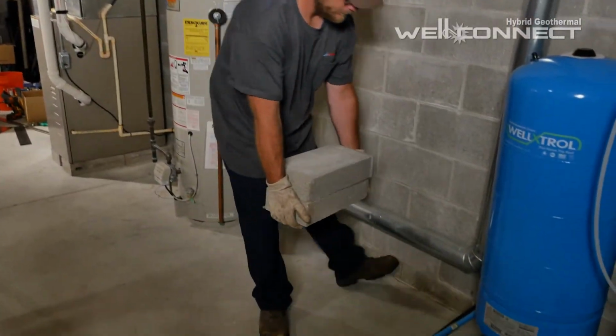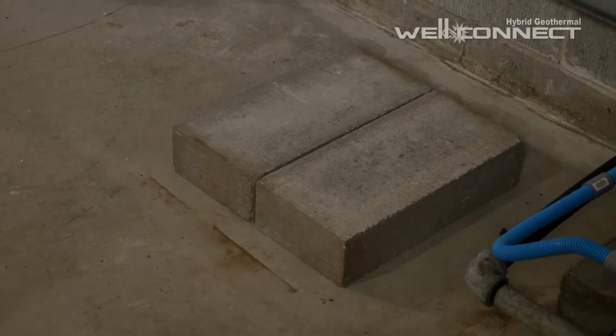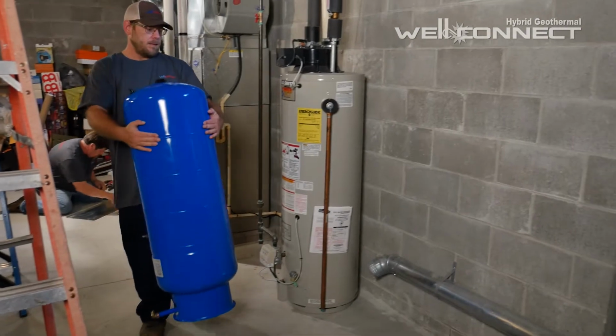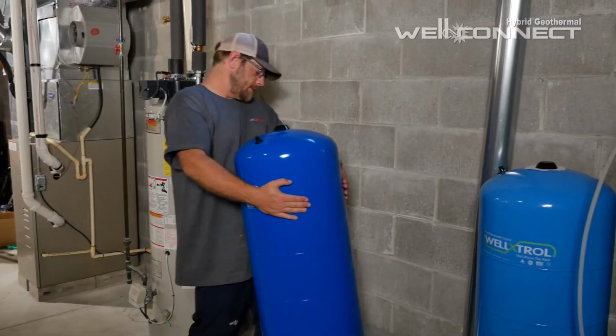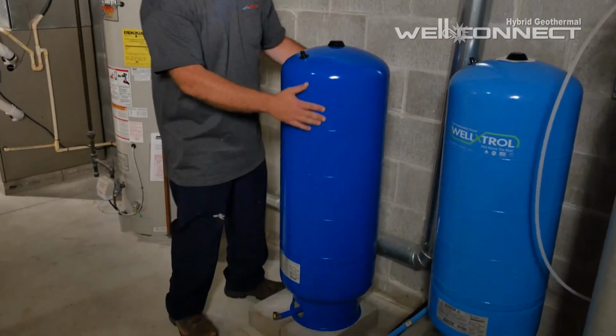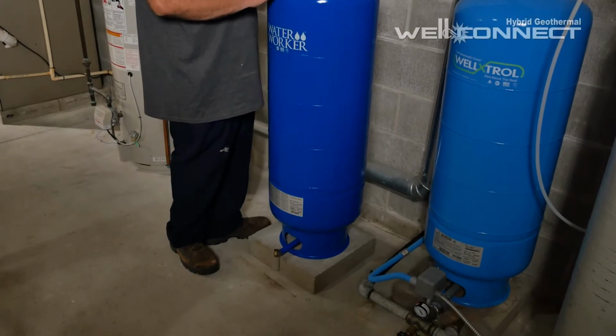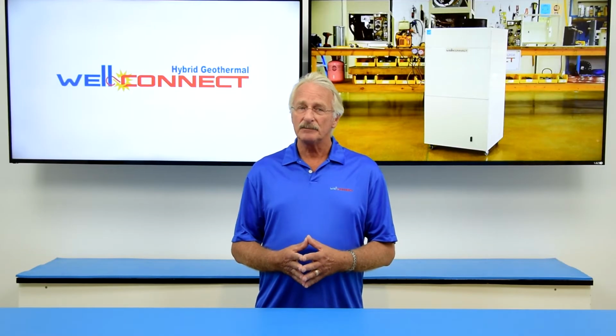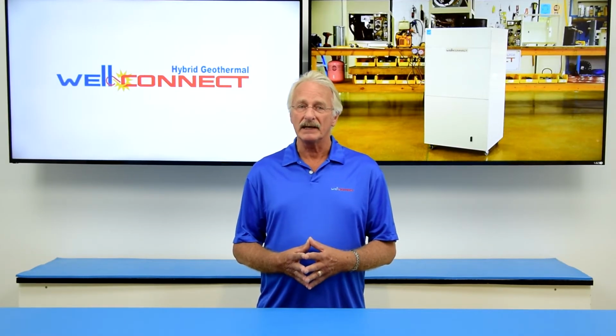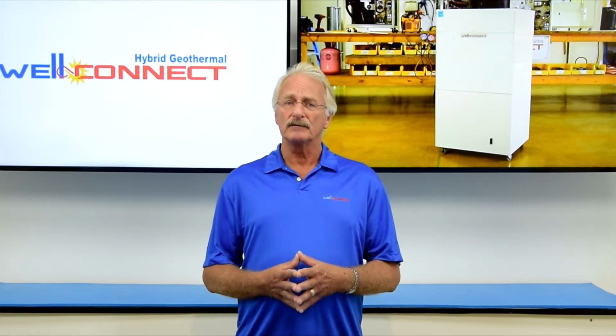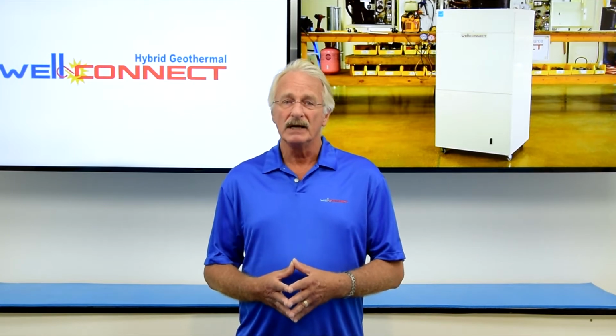In most installations, it is necessary to replace the pressure tank with a larger model or add an additional pressure tank to the existing tank to provide a greater volume of water drawdown, which will reduce the number of times the well pump cycles on and off. Ideally, the pump will remain off for about 10 minutes and then run for 2 minutes or so to fill the tanks back up. This 12-minute pump cycle means the well pump would cycle 5 times per hour, or at most 120 times per day, well below the 250 to 300 maximum cycles per day recommended by most submersible pump manufacturers.